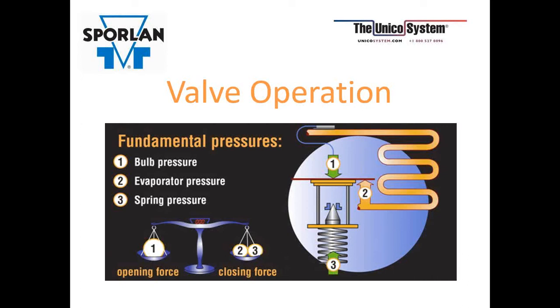The bulb pressure pushes down on top of the diaphragm, flexing it so it can push against the buffer plate, pushing the push rods to push the pin out of the port and opening the valve. Number 2, evaporator pressure. That pressure comes from the external equalizer connection from the suction line at the outlet of the evaporator. This pressure is applied under the diaphragm and helps close the valve.